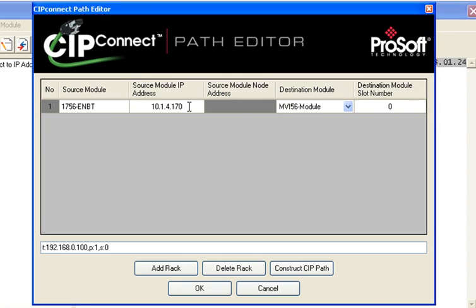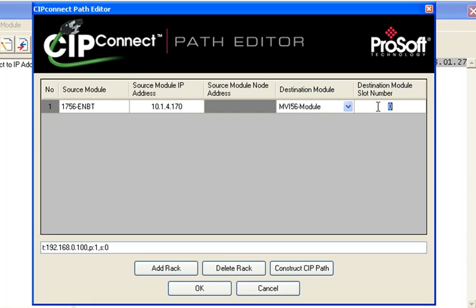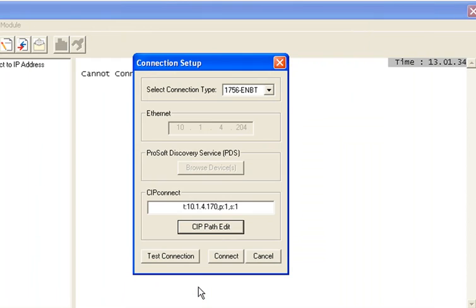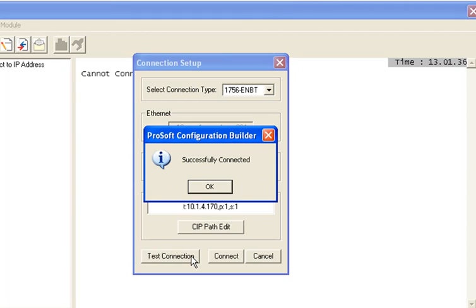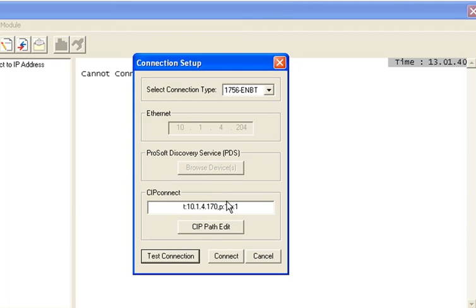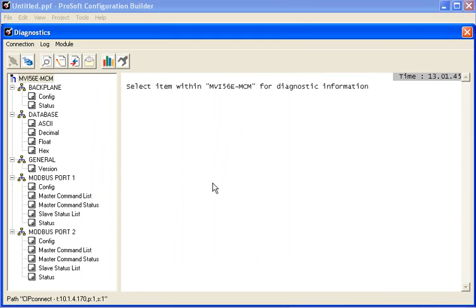And I know that I'm going to a 1756 module and I know that my module is in slot number 1. So I'll click on Construct CIP Path and then click OK. Now I can click on Test Connection and that connection is also good. So we'll click OK there. And now I'll click on the Connect button and you'll see that we're connected.